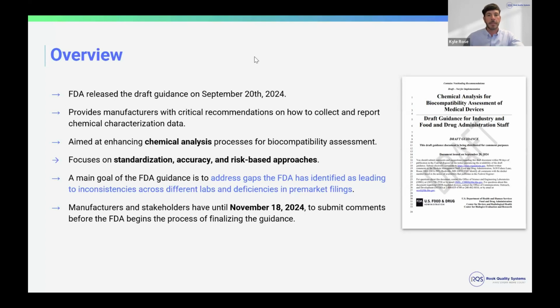There have been gaps in both the testing as well as testing between labs, and this is related to different deficiencies in pre-market filing. So this guidance is intended to align the testing process, align what's required for different types of devices, and ensure that there is kind of consensus going forward that everybody that is submitting chemical analysis related to biocompatibility is doing it in a similar fashion and doing similar types of testing.